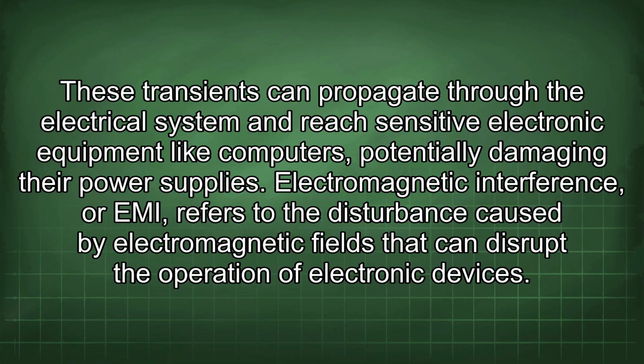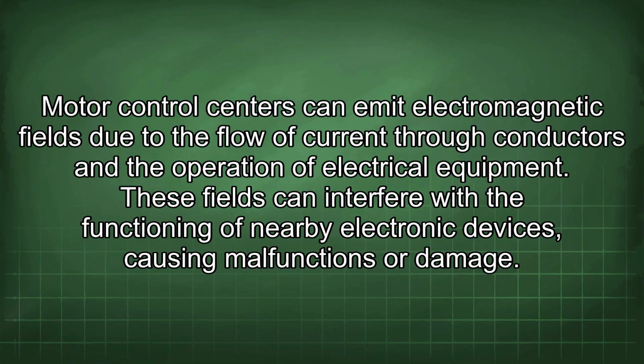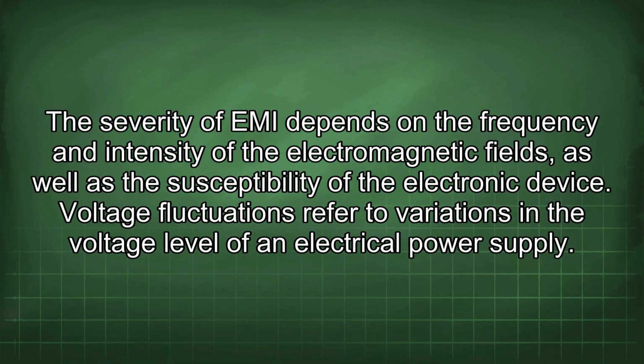Electromagnetic interference, or EMI, refers to the disturbance caused by electromagnetic fields that can disrupt the operation of electronic devices. Motor control centers can emit electromagnetic fields due to the flow of current through conductors and the operation of electrical equipment. These fields can interfere with the functioning of nearby electronic devices, causing malfunctions or damage. The severity of EMI depends on the frequency and intensity of the electromagnetic fields, as well as the susceptibility of the electronic device.